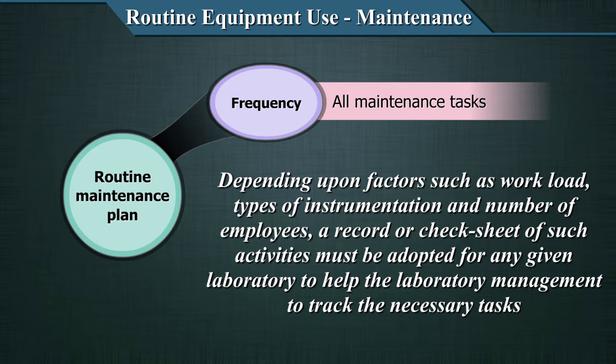It is important that laboratory management tracks these tasks to make sure things are getting done. The documentation of maintenance is a very important aspect. Maintenance qualification starts with the maintenance plan, which has to be developed as the equipment arrives in the laboratory as part of the OQ. It has to be implemented and documented in specific formats designed for the purpose.